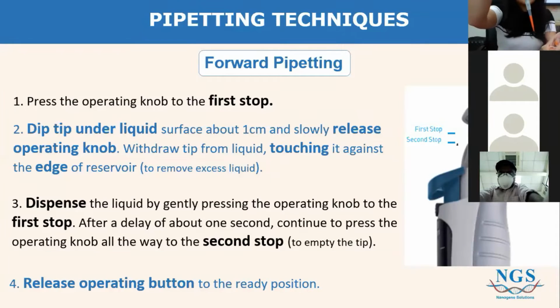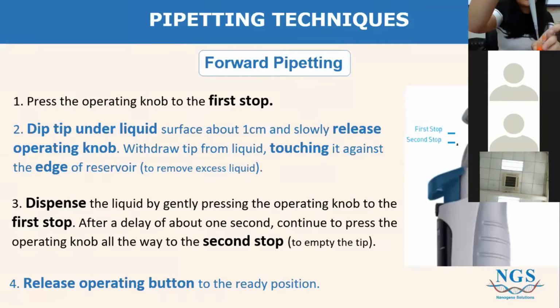All right. So I have it, and then once you aspirate it, it's kind of important to make sure that there's no excess liquid. So one good tip is to just touch it against the surface of your reservoir. All right, so you want to dispense your liquid. So with that, you just gently press the operating knob to the first stop. All right, and then after a delay of 1 second, continue to the second stop. So there you go, you've emptied your tip. All right, so in mid-air, you just slowly release your operating knob to a resting position.